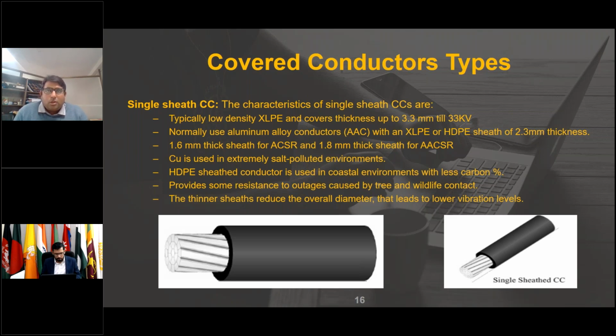If we use copper, it is usually used in extremely salt-polluted environments, usually in what we call sea areas or coastal areas. Basically, we mostly use copper because it's an extremely salt-polluted environment. So HDPE sheathed conductor is used in coastal environments with less carbon percentage. It provides some resistance to the outages caused by tree and wildlife contacts. And the thinner sheath reduces the overall diameter and it leads to a lower vibration level. Those vibration levels may cause a lot of difference. So you can see the single sheath covered conductor just below this description.